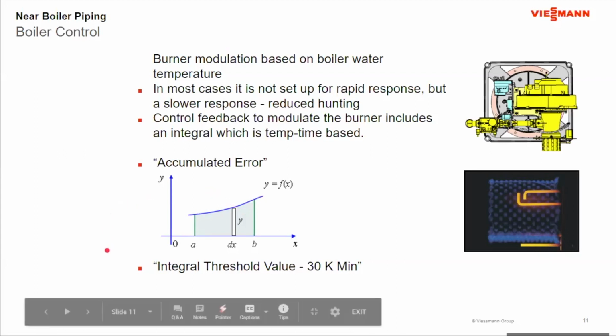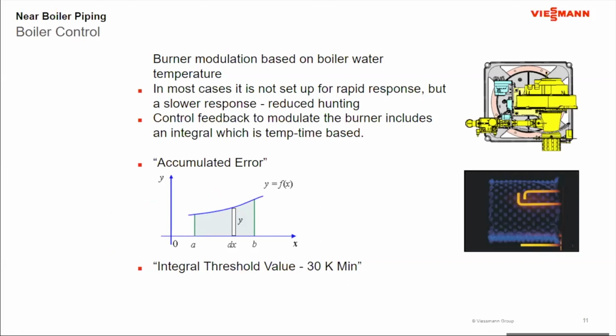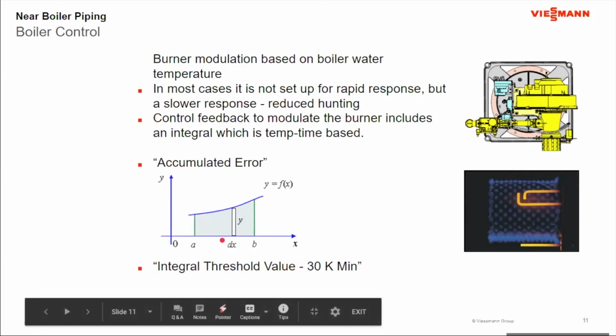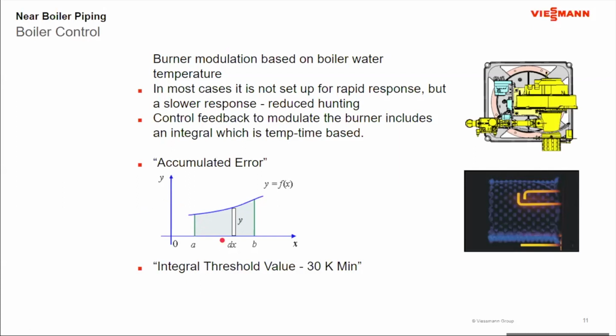In our control logic, you'll see it listed in the coding as integral threshold value. Our default value is 30 K minutes, and the K is for Kelvin minutes: temperature and time. So when we look at the operation of the boiler, this is what we're dealing with from a control standpoint.